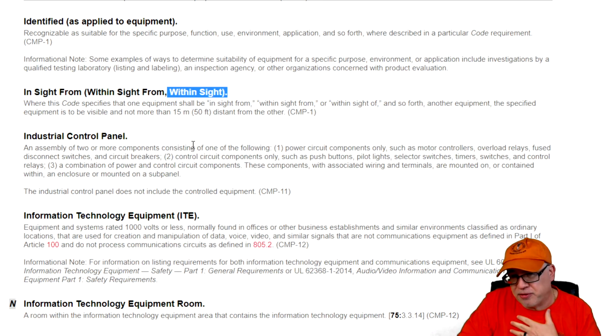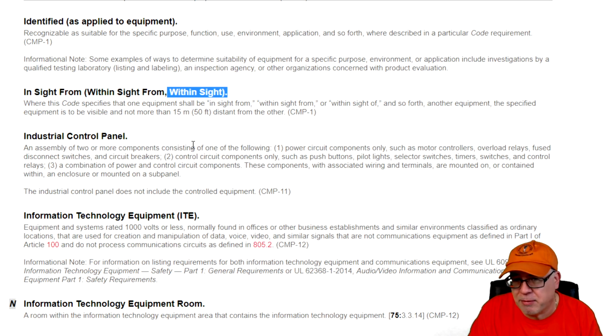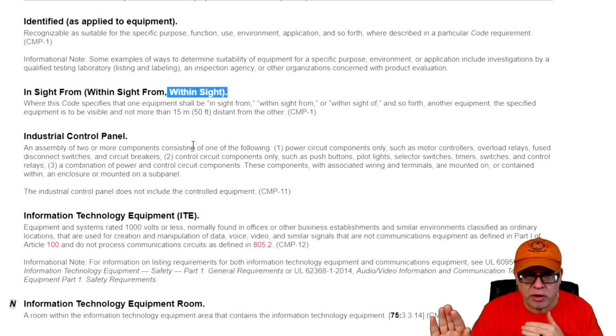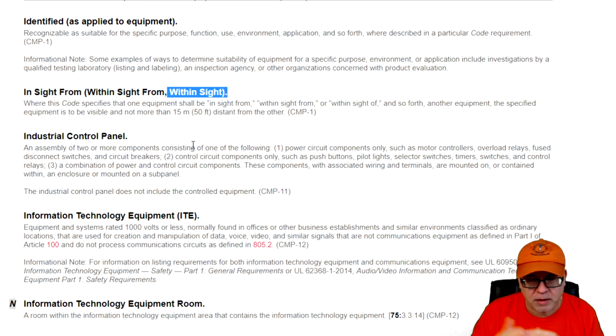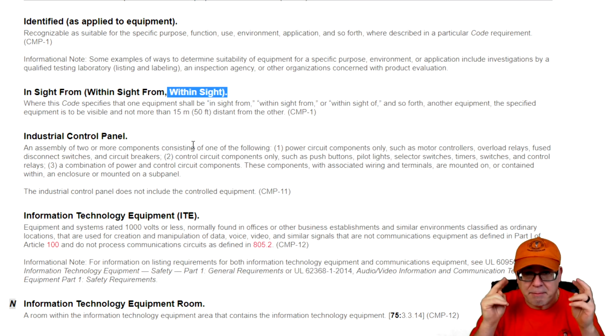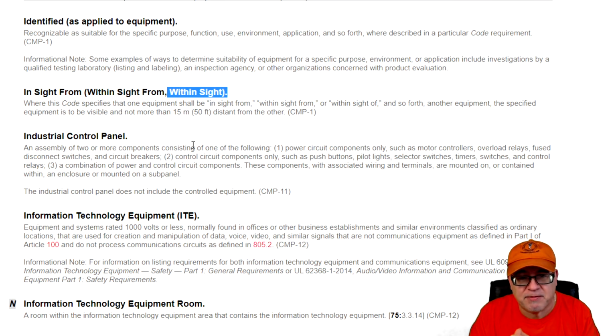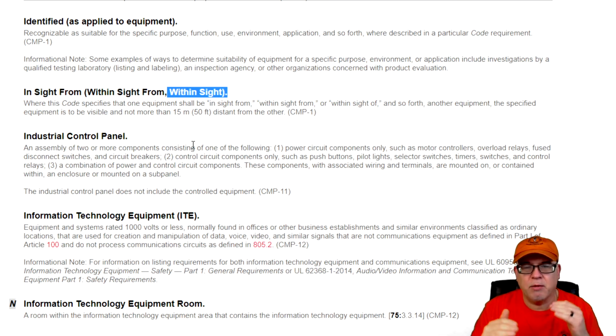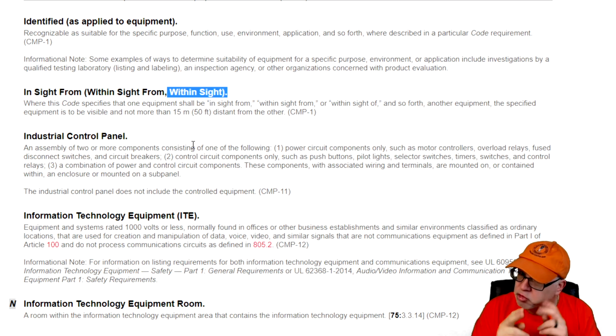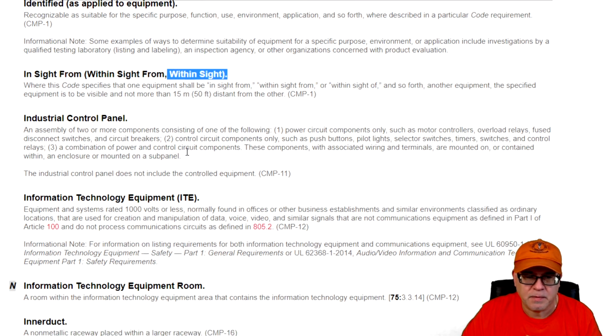From a code person's perspective, it's got to be within 50 feet. It can't be around a corner and still be only 25 feet away and say, hey, it's within 50 feet. Nope. If I can't see it, it's not within 50 feet in my mind. It is physically within 50 feet, but it is not when it comes to the NEC. Okay? Two components there you have to keep up with.